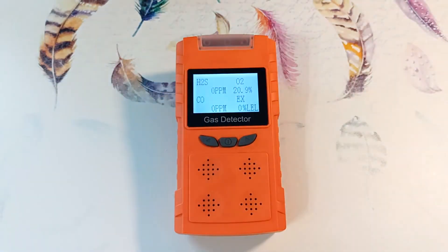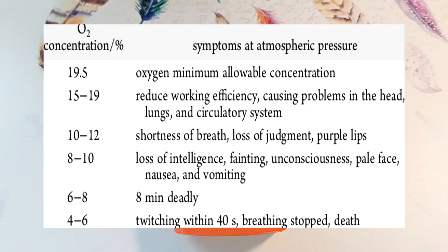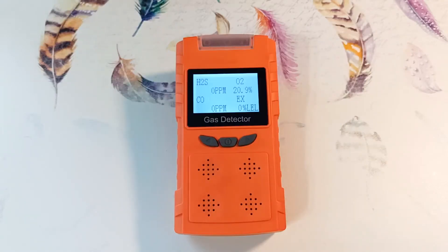O2 is oxygen. Its standard concentration in the air is 20.9%. Both a lack of oxygen and a high concentration are dangerous. If the concentration drops below 19.5%, rapid breathing and dizziness begin, and less than 7% leads to coma or death. If 23.5% is exceeded there is a risk of ignition. If the oxygen concentration goes outside 19.5% to 23.5%, the device triggers an alarm.